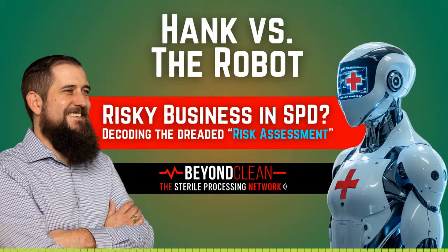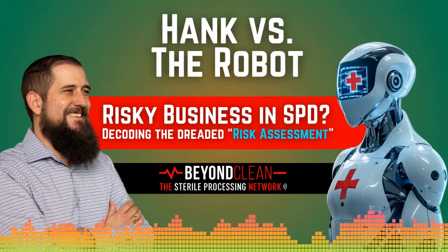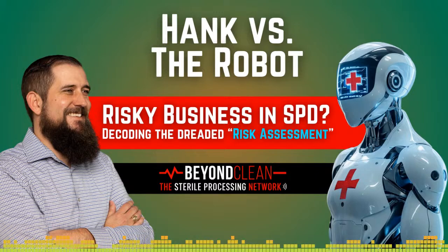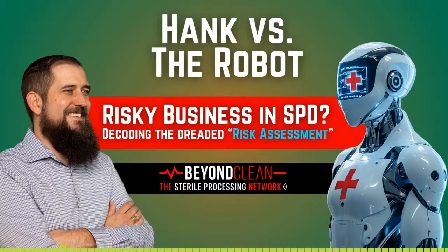Sure thing, Hank. That article from the American Journal of Infection Control is a great anchor for this discussion. It focuses on the process of troubleshooting failed sterilization loads with a strong emphasis on risk assessment as a practical tool. The authors break down how to identify potential process failures like wet packs or mechanical issues, and then guide readers on assessing the risks these failures pose to patient safety and compliance.